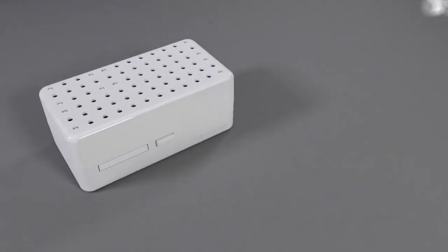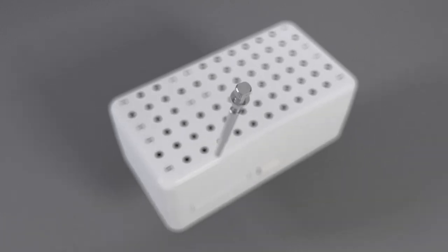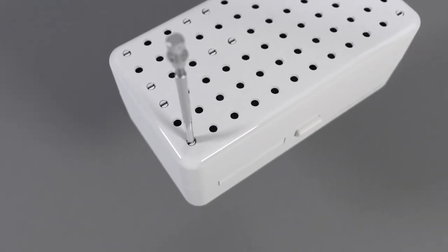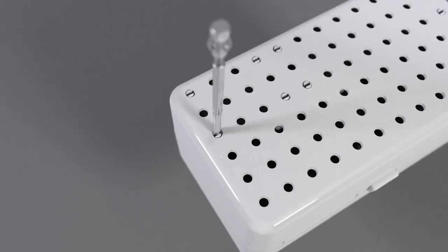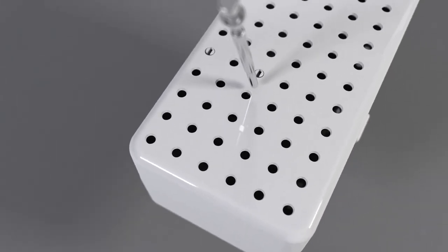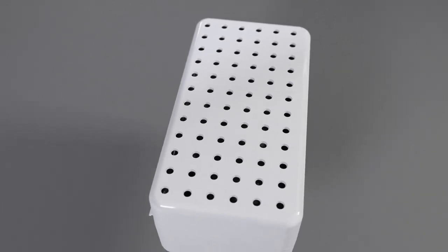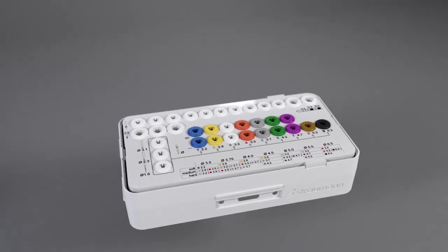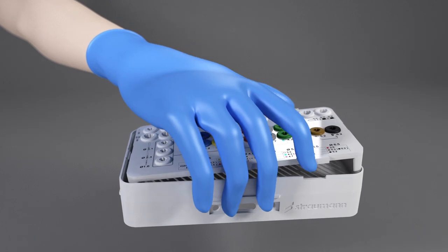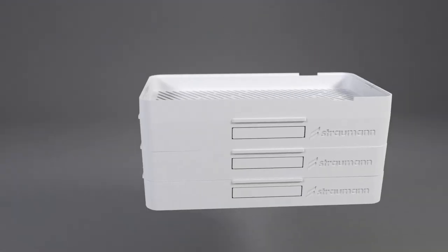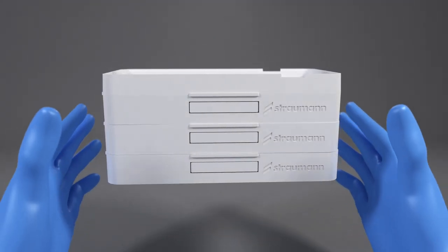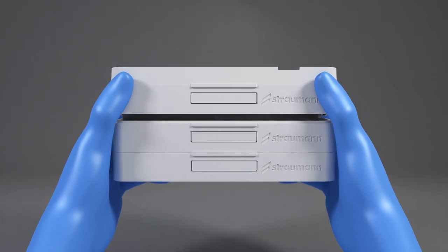Disassemble the cassette and clean all parts individually. Take out the A module trays with the inner part of the ratchet, pushing out the connectors from the back. The B module tray is lifted out at the holders. To separate B and C module, gently pull on one side by hand to break the connection.